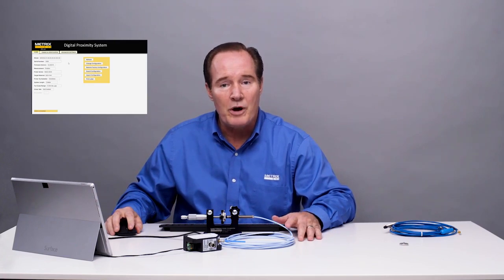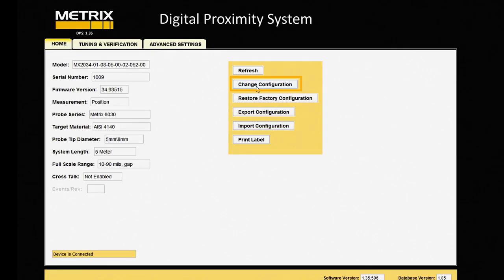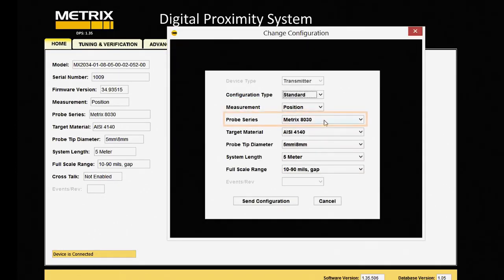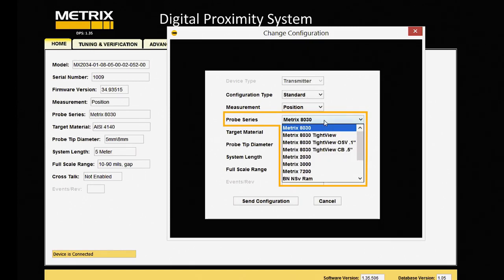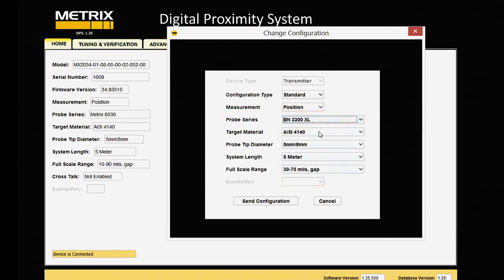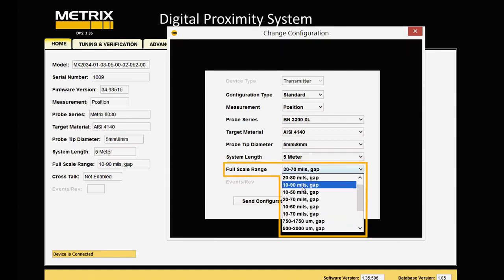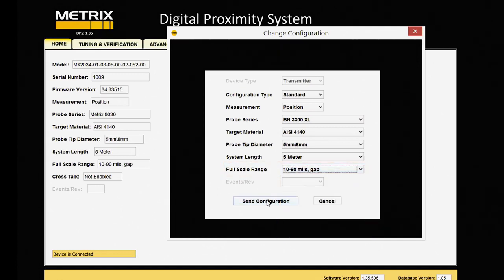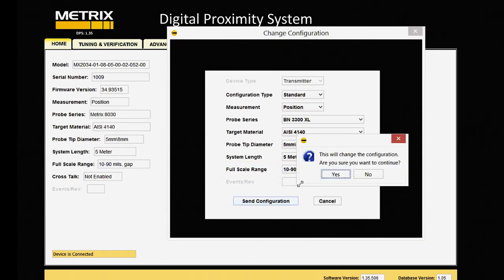And what we'll do is we're going to change the configuration in our digital proximity system software. So we'll go to change configuration, and we're going to change the probe series from MX8030 to BN3300XL. I'll look for that. BN3300XL, I find that, and it's an 8mm probe with a 5-meter cable, and we'll set the scale range, because we're working with the transmitter, to 10 to 90. Then we'll send that configuration.